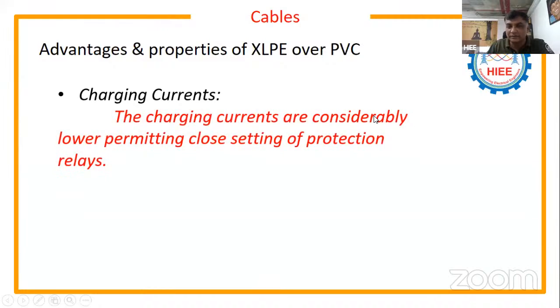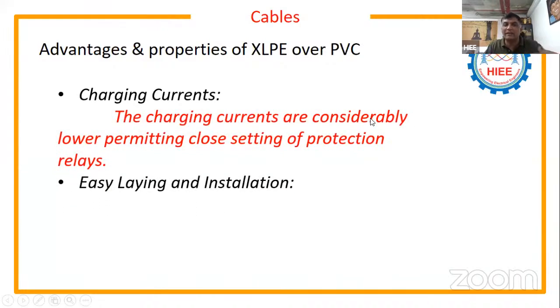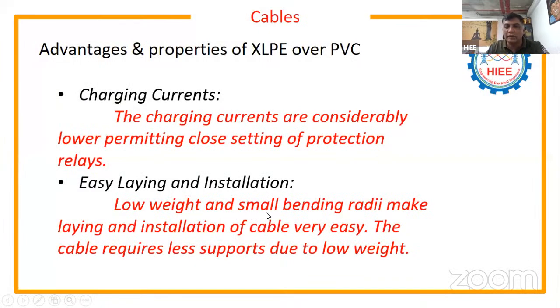And charging currents. Okay, so these are the various advantages. Easy laying and installation, because going with XLPE makes laying easy during the installation of the cable. A low weight and a small bending radius make laying and installation of the cable easy, because generally when you're laying cables, the bending radius should be easy. XLPE cable has a smaller bending radius than PVC cables. That makes the installation of the cable very easy.